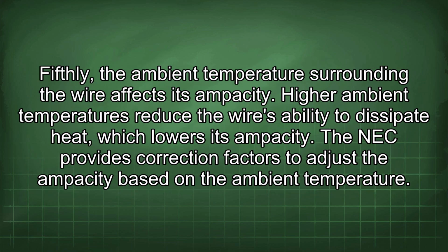Fifthly, the ambient temperature surrounding the wire affects its ampacity. Higher ambient temperatures reduce the wire's ability to dissipate heat, which lowers its ampacity. The NEC provides correction factors to adjust the ampacity based on the ambient temperature.